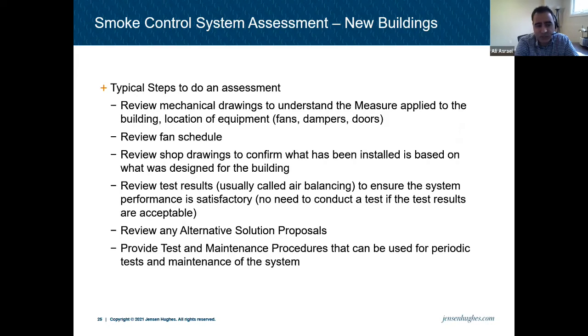We review the fan schedule to get an understanding of the size of the fans and their location. This is to confirm that the system was designed properly. Say you're an engineer involved here, reviewing the mechanical, and the designer designed a 10,000 CFM fan for this. You go to the building code, review the requirements of the measure that was applied to the building, and based on the number of stories and whatnot, you double check against the fan size, and you see, okay, the designer is right. They designed the system properly and it matches. And just because the system was designed properly, it doesn't mean that it was installed properly on site as well.